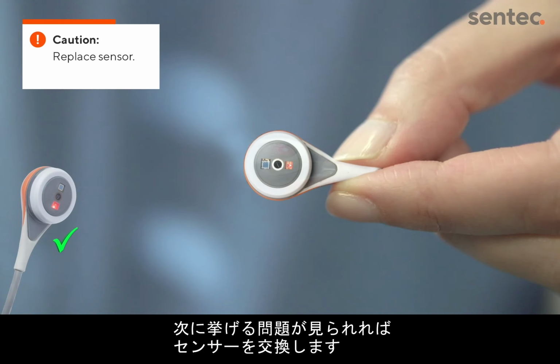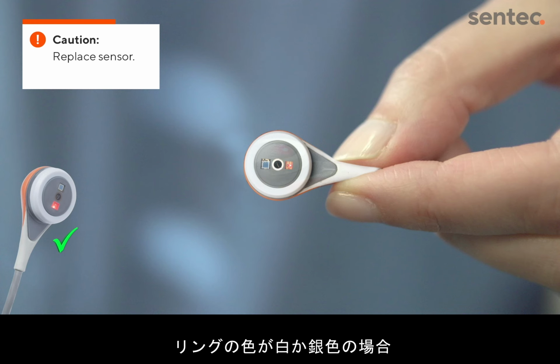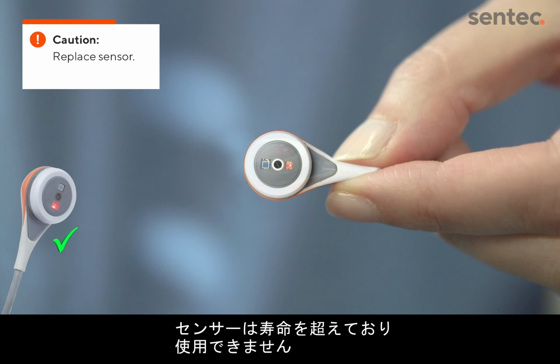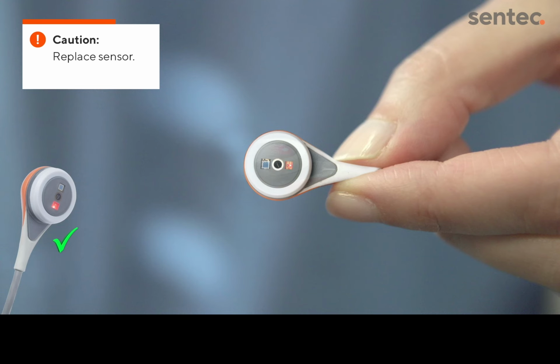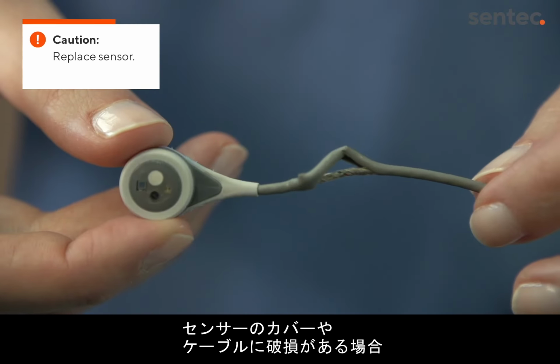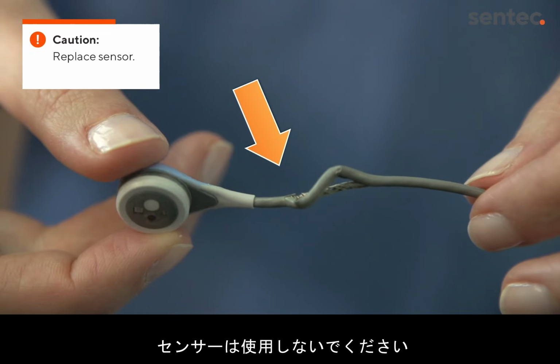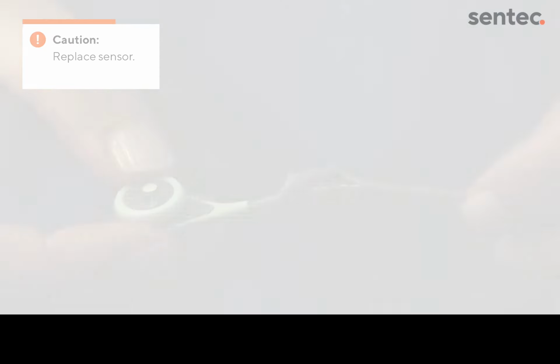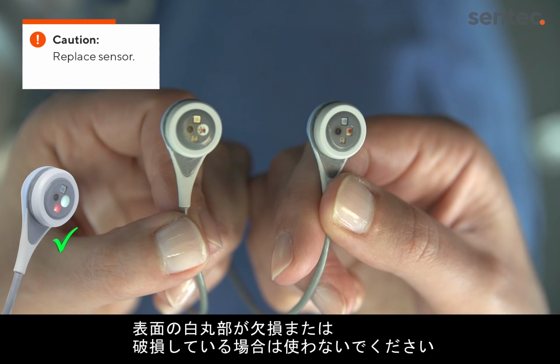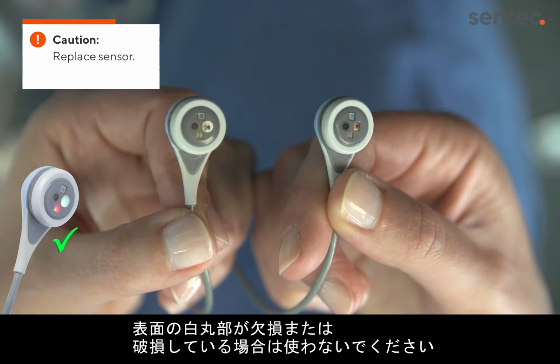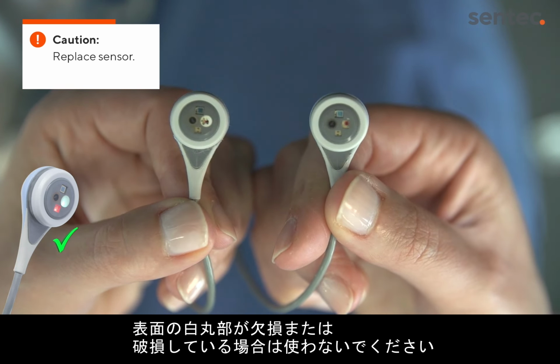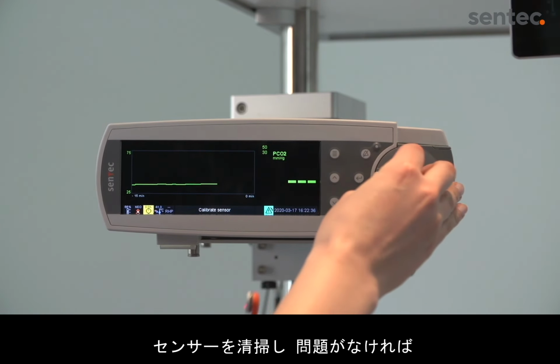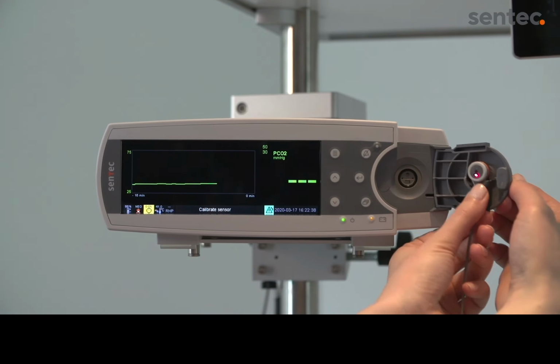Inspect the sensor for the following issues, which require sensor replacement. If the ring has a white or metallic luster, the sensor has exceeded its lifetime and cannot be used. If there is any damage to the sensor housing or sensor cable, do not use the sensor for patient monitoring. In the case of the OxyVent sensor, do not use the sensor if the white spot on the sensor face is missing or damaged.